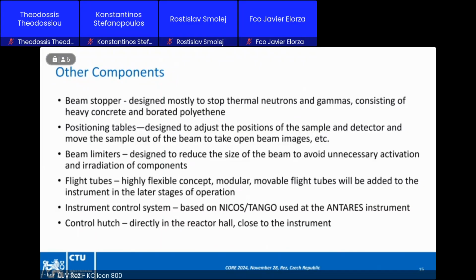If you want to perform tomography, you need some positioning tables. So you need to be able to move your sample in the position where you need it. You need to be able to rotate your sample. So you need stuff like that. So we already designed these components to use with the detector system. I also mentioned beam limiters, so it's just to reduce the size of your beam so your components don't get activated. You can also use flight tubes, so we might add them in the future, but for now it's not really necessary because the distance between the shutter and the detector is not that high, so you don't really need a flight tube. There won't be that big of a neutron loss.